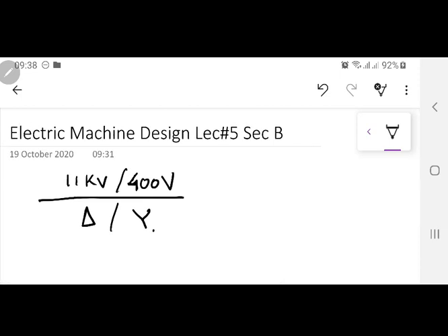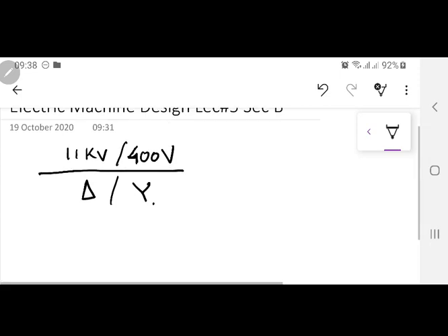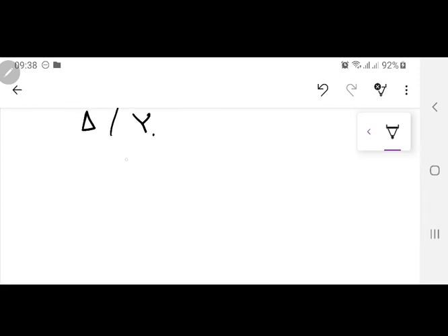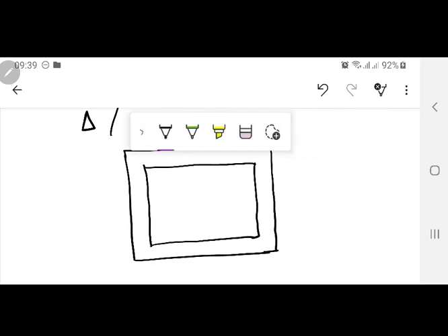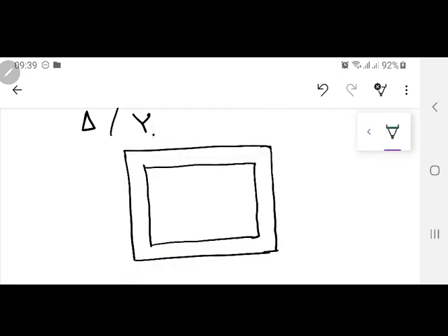So you can go on with me in what I'm doing over here. But before I move on towards the total winding design and try to fill out these tables in front of you, a very important thing is that if you are designing a core type transformer, and since distribution type transformers are mainly core type, so if this is the core type, I'm talking about single phase, you can extend that to 3-phase also. When you are going to have a 3-phase transformer winding, I have told you previously also that the low voltage winding is going to be done first, and the foremost reason is that the low voltage winding requires less insulation with the core.